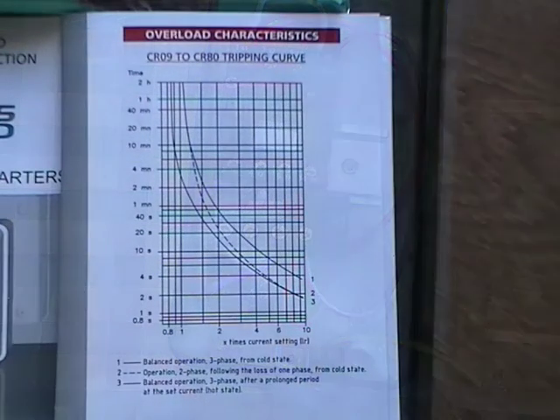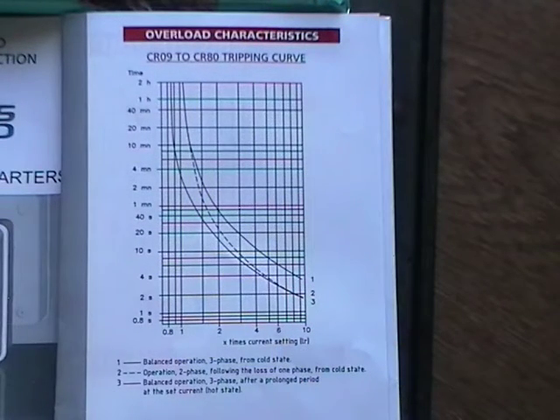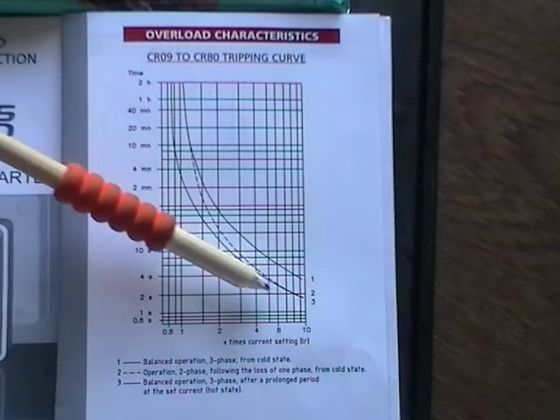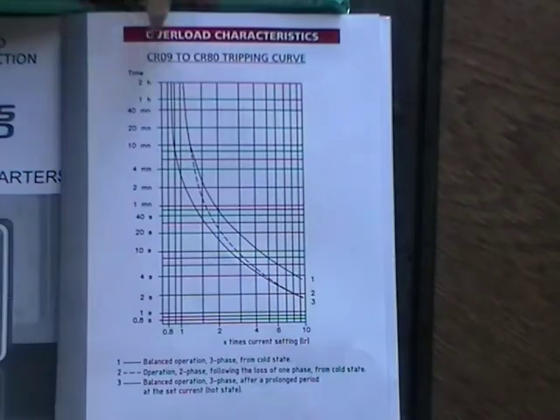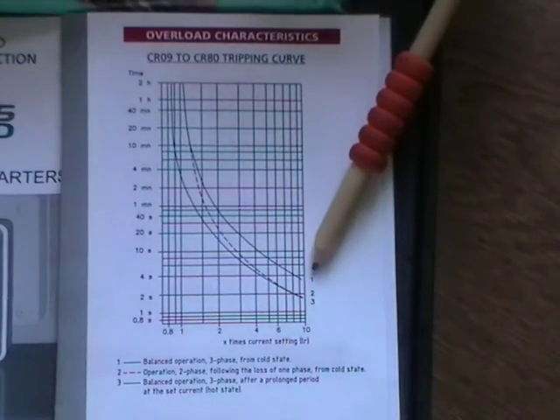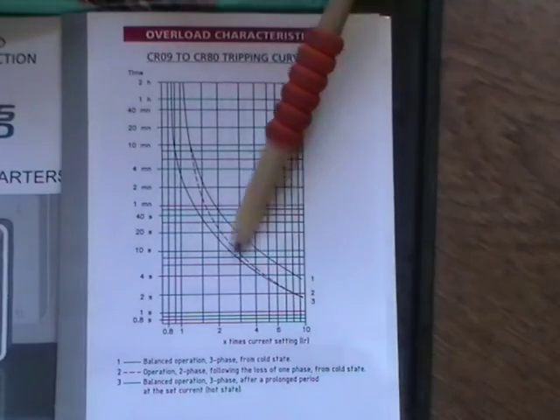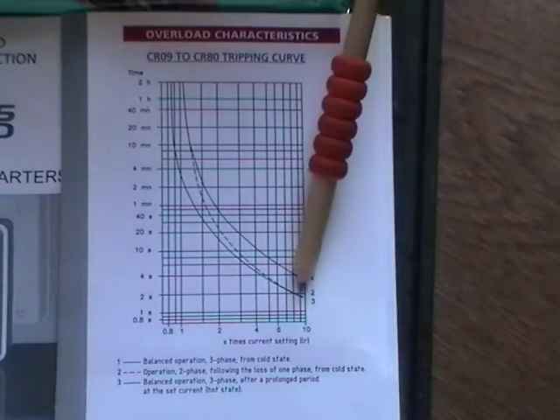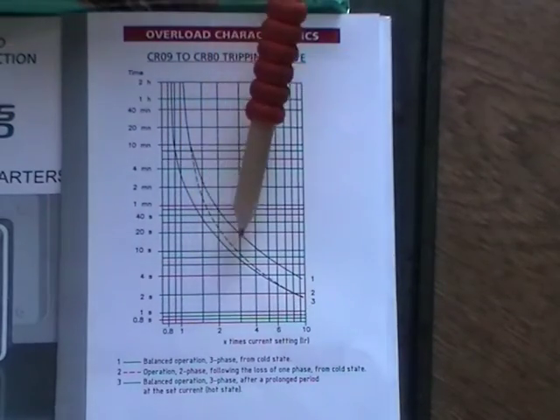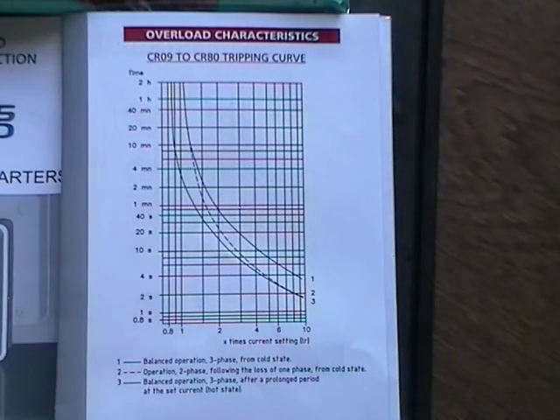This chart is the overload characteristics for this trip that's installed in this motor starter. I will zoom in a minute on it, but generally we've got 2 curves, one there and one there, labelled. That one's labelled number 1, that one's labelled number 3. There is one that goes from the end of one to part way along the other and dotted and labelled number 2, but we can ignore that one.